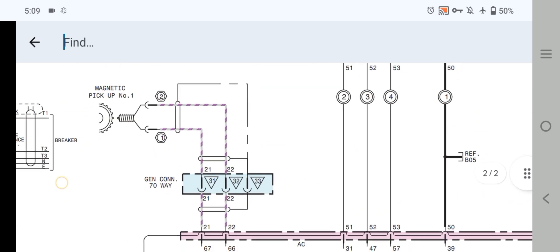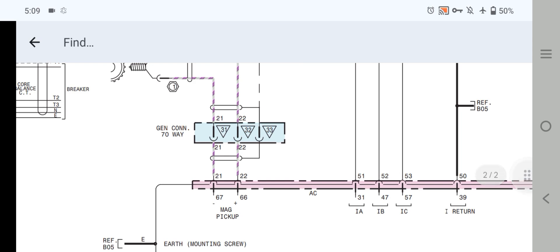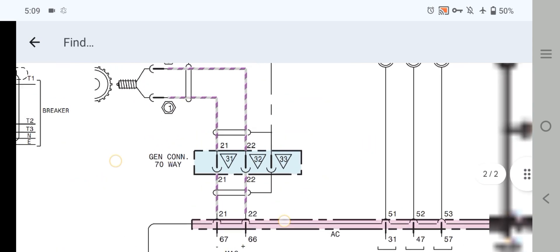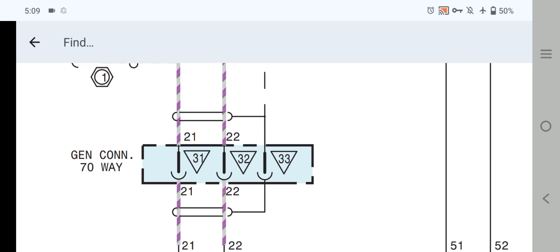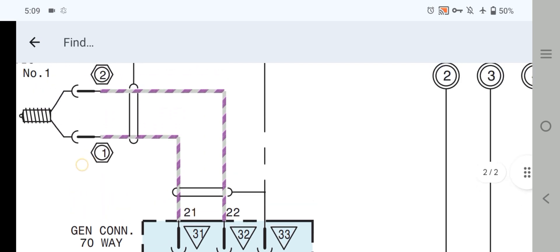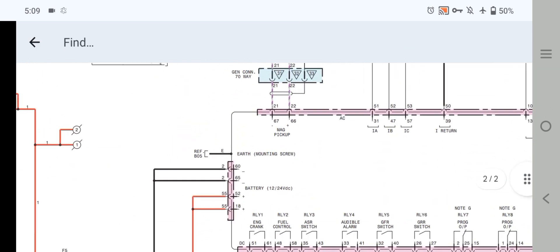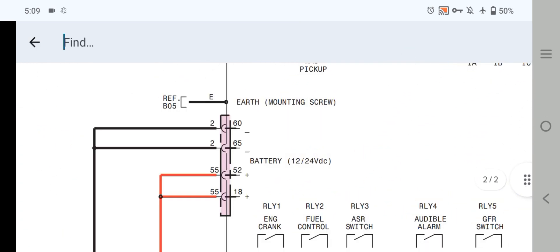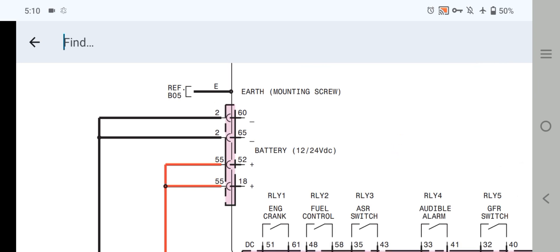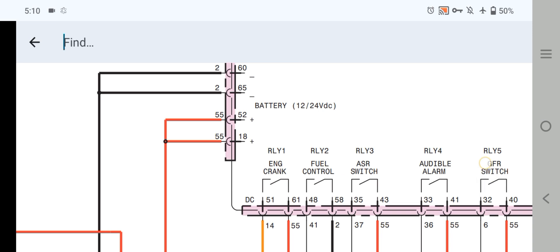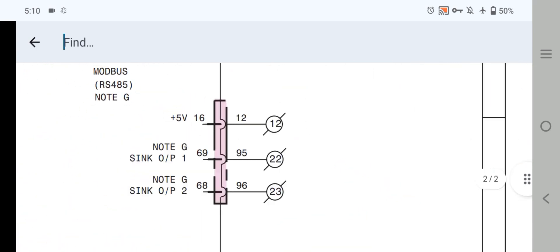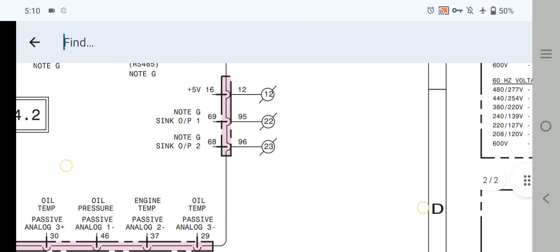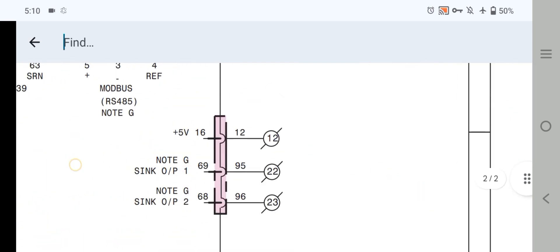As you can see here, this is the MPU — Magnetic Pickup Unit — via the generator 70-pin connector: pin 31, pin 32, and pin 33 is the shield wire. Pin 20, wire number 21 and 22, is going into the EMCP. Also, pin 60 and pin 65 are battery negative inputs to the EMCP controller.